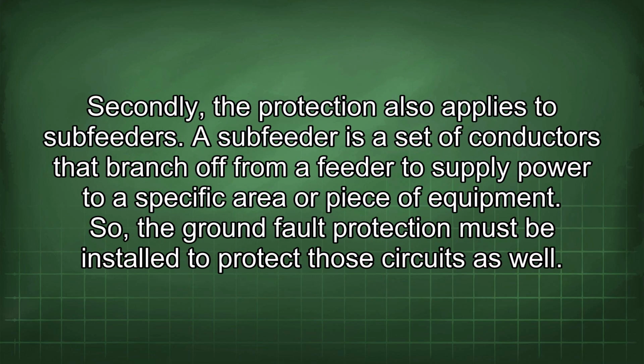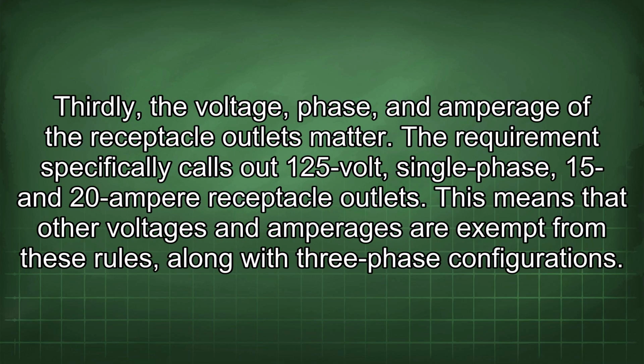Secondly, the protection also applies to subfeeders. A subfeeder is a set of conductors that branch off from a feeder to supply power to a specific area or piece of equipment. So, the ground fault protection must be installed to protect those circuits as well. Thirdly, the voltage, phase, and amperage of the receptacle outlets matter. The requirement specifically calls out 125-volt, single-phase, 15 and 20 ampere receptacle outlets. This means that other voltages and amperages are exempt from these rules, along with three-phase configurations.